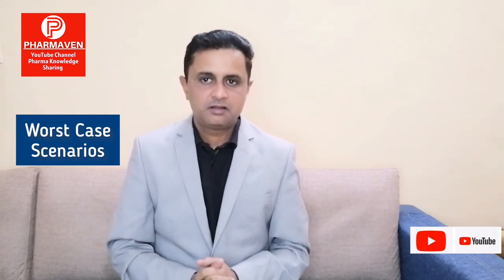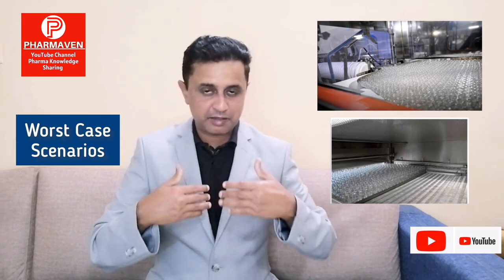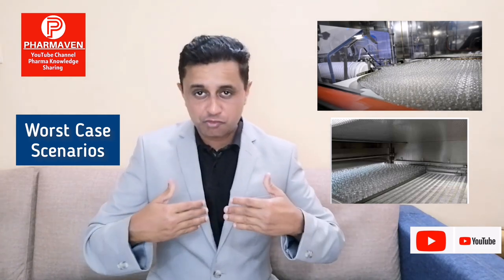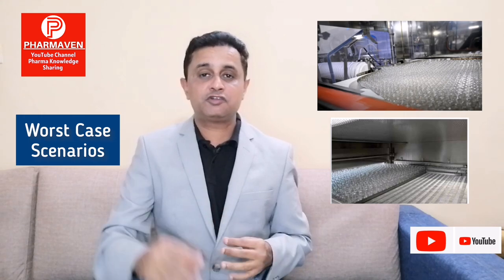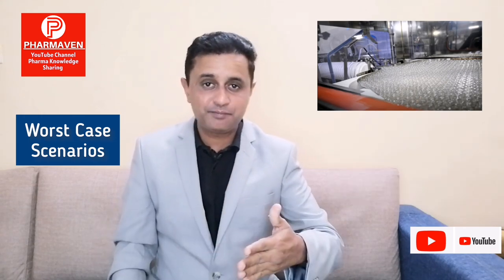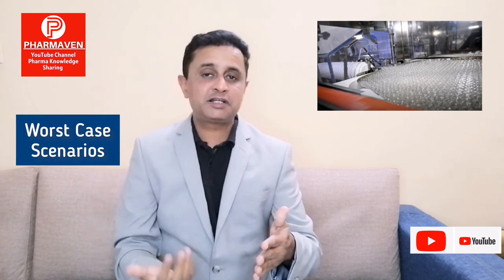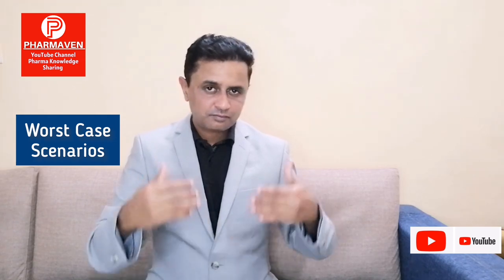What is my third worst case? Again in the middle we have to place the sensor in the same manner as we kept in the initial path, to cover the entire width of the conveyor. Now what is my third worst case? It is the end of the vials, when my last row of vials is going inside the tunnel, when my entire washing machine operation is completed. That end row is my worst case, because now my tunnel conveyor is getting emptied. So air will flow toward the conveyor mesh rather than going inside the vial, and it will pose the challenge that it will not get enough heat exposure. So the end of my tunnel will be again the third worst case in terms of proper heat exposure.